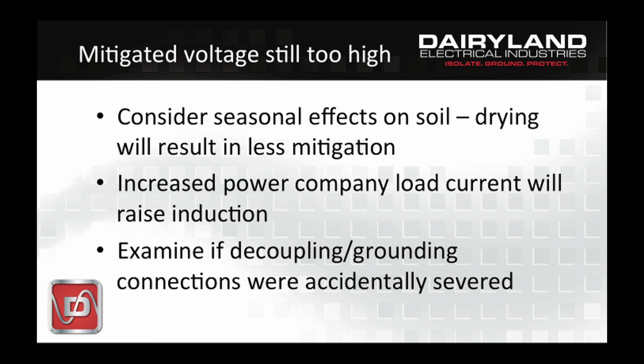In fact, be very cautious when you take readings. The time of day that you take the reading and the season of the year that you take the reading can greatly affect the reading you get and the results or the assumptions that you make. Time of day and power loads will swing wildly, and seasonally will also vary. And so you really want to trend induced voltage over time and leave a recorder out there to obtain voltage values.